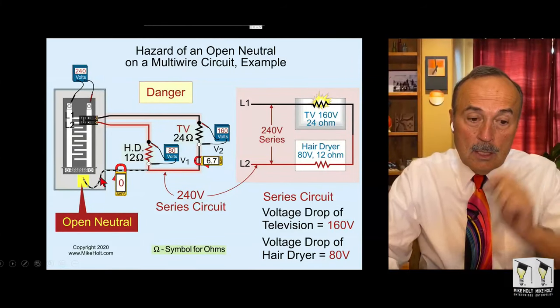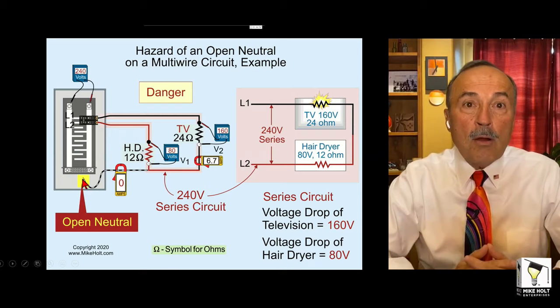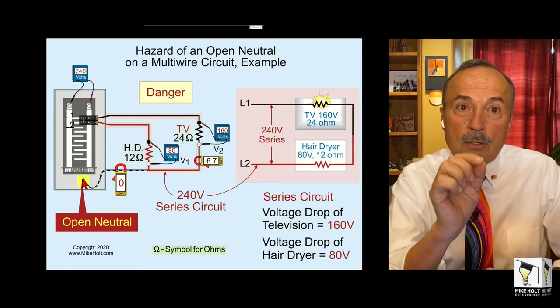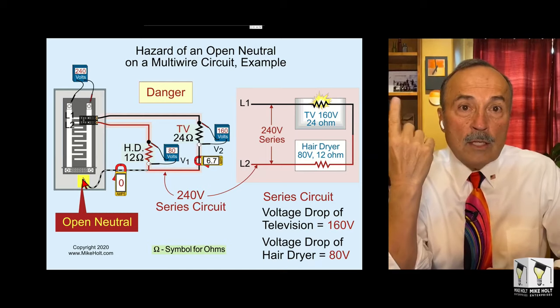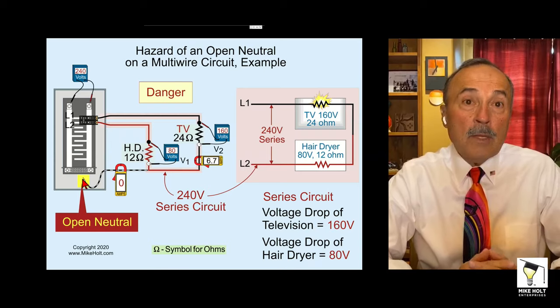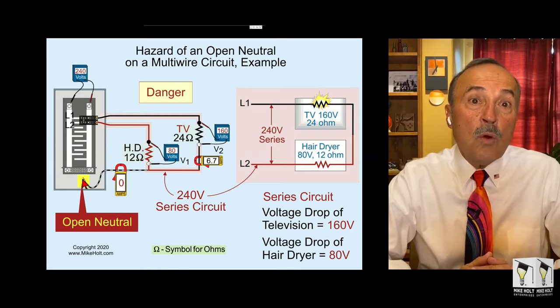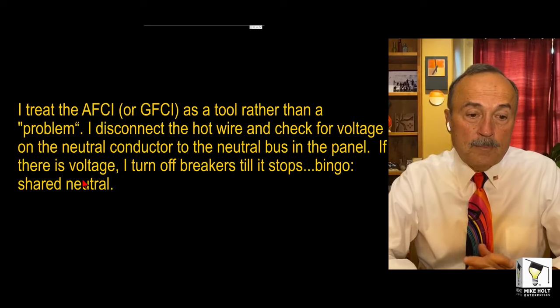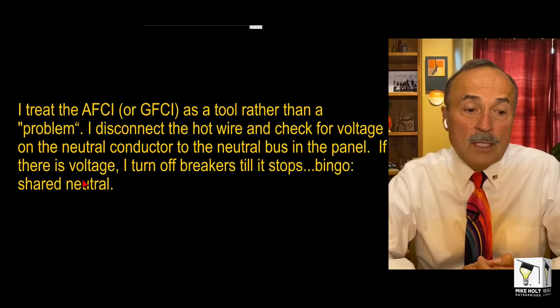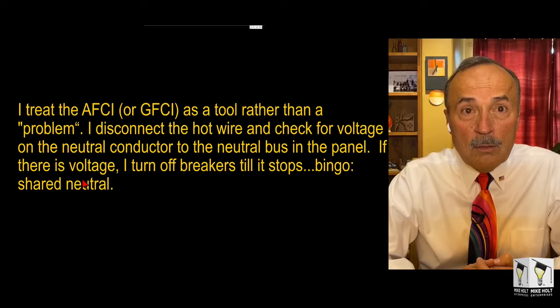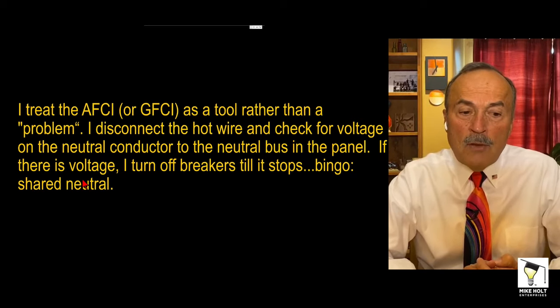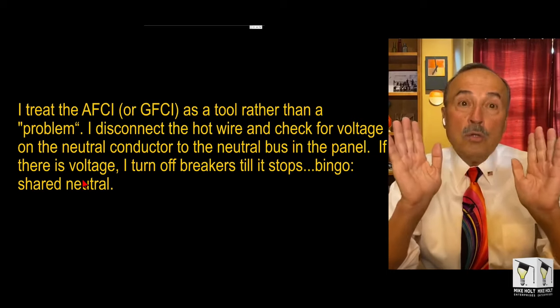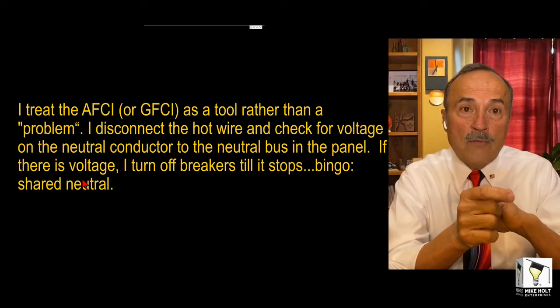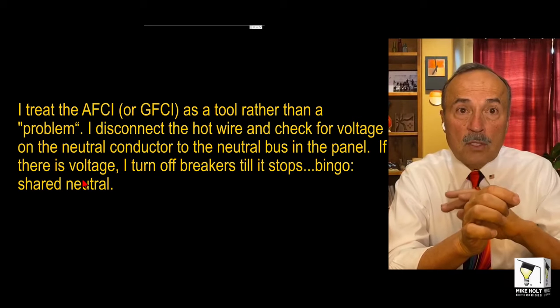My head is going, wait a minute. You don't want to do that, because that might be part of a multi-wire branch circuit. And the moment you take that neutral off, you don't know how the wiring is going to be, whether there are other circuits connected in there in a multi-wire branch circuit configuration, and then you will wipe out the equipment. So back over here. Hey, I treat the AFCI, GFCI as a tool rather than a problem. I disconnect the hot wire off of that breaker that was tripping the electronic breaker, and check for voltage on the neutral conductor to the neutral bus of the panel. Don't do that. You never take a neutral off of a neutral bus because you don't know if it's part of a multi-wire branch circuit.